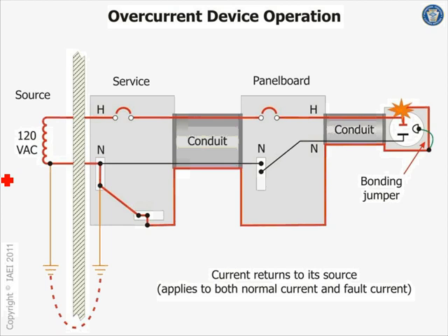That's why we bond the neutral, because we're going to go to this reference point right here. We bond the neutral, so it jumps, takes a free ride over the neutral in the service back to the source. Now, that's 99% of it. There will be close to 1% that goes through Mother Earth, especially in Minnesota when it's wet, right, and really good low impedance here. You'll have some current going through here. The NEC code book says, ignore this. This does not exist. We don't want you to depend on this.